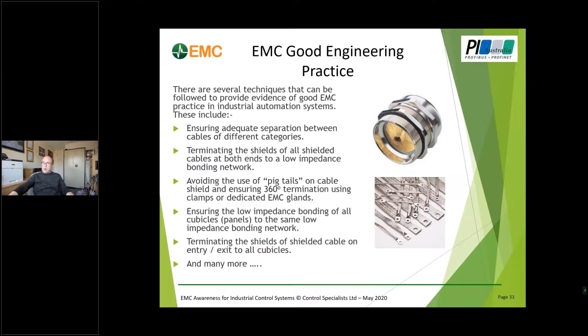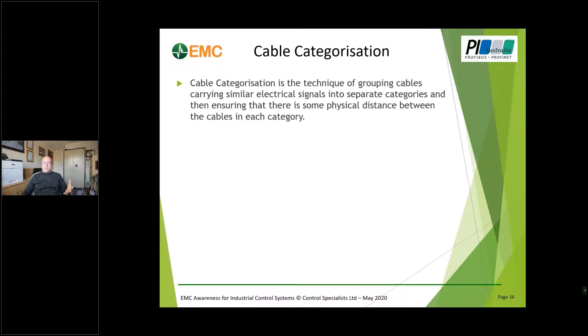We have the idea of cable categorization and segregation - an installation is likely to have many different cables, some low voltage, some high voltage, some low current, some high current, etc. Designers try to categorize them so they can bunch similar cables together but run them separately from other cables. So we might have a simple categorization: category 1, 2, 3 and 4 - sensitive cables in 1, low voltage in 2, high voltage in 3, and anything from lightning strikes in 4.